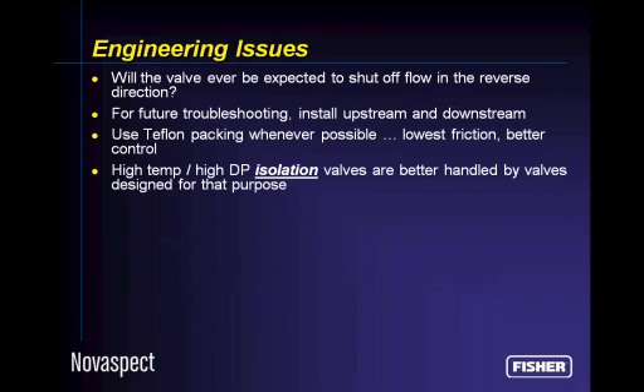I was at a power plant in Wisconsin not too long ago, and the customer said, Mike, I forgot the process. There's a process. I think it involved hydro testing. He said, we actually are going to need this valve to shut off in the reverse flow direction. Believe it or not, most control valves by nature do not do that very well. They can shut off pretty well in one direction, but unless we arrange for it, they don't shut off well in the other direction, and we end up collapsing elastomeric parts. We can damage them. So if it's going to have to flow in the reverse direction sometime, tell us.